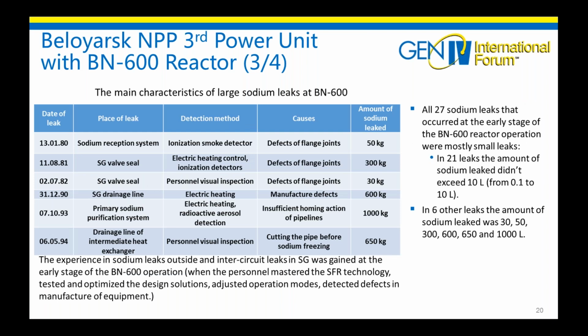The experience in sodium leaks outside and inter-circuit leaks in the steam generator was gained at the early stages of the BN-600 operation. All 27 sodium leaks that occurred at the early stages of the BN-600 operation were mostly small leaks. In 21 leaks, the amount of sodium leaked didn't exceed 10 liters. It was from 100 milliliters to 10 liters. In 6 other leaks, the amount of sodium leaked was 30, 50, 300, 600, 650, and 1000 liters. This table contains the main characteristics of these sodium leaks.